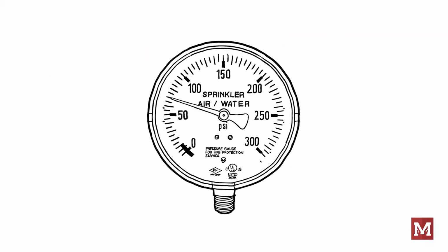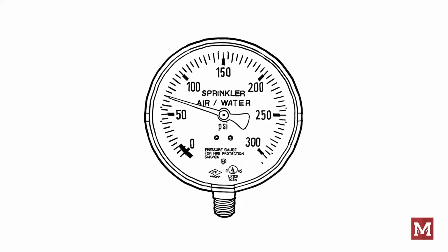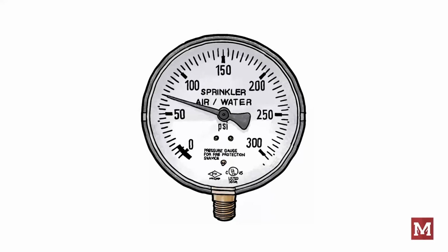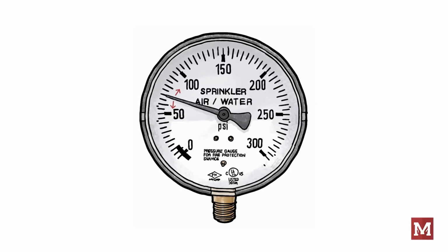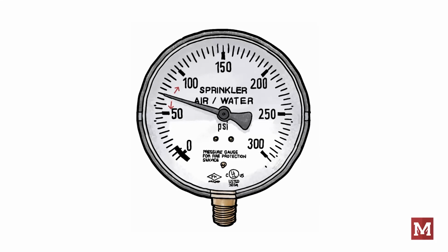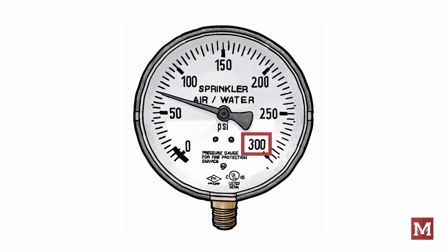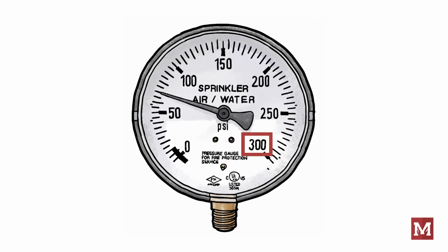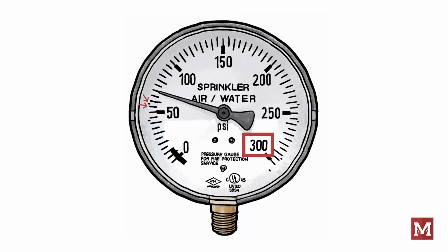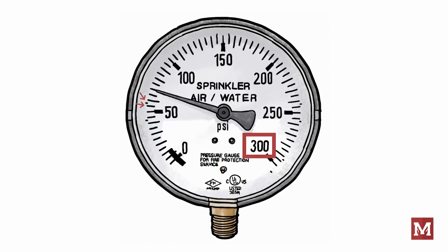Now let's see what introducing a little bit of error would have meant on these 2 tests. Just take, for example, the reading on a single gauge alone. If you've ever run or witnessed a flow test, you know that analog gauges like to bounce around. It's not uncommon to have a needle that bounces maybe 2, 3, or 4 psi. Not only that, if you are using a 300-pound gauge and we're trying to distinguish between a 57 or 58 psi reading, well, that's extremely difficult to read. There's some error just in the bouncing of the needle itself.